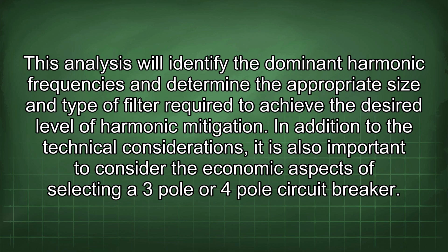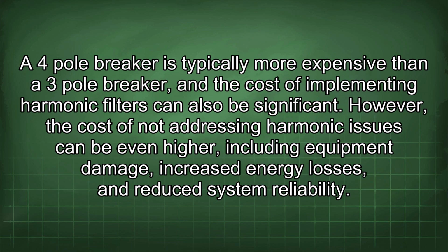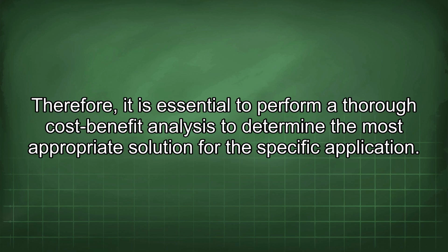In addition to the technical considerations, it is also important to consider the economic aspects of selecting a 3-pole or 4-pole circuit breaker. A 4-pole breaker is typically more expensive than a 3-pole breaker, and the cost of implementing harmonic filters can also be significant. However, the cost of not addressing harmonic issues can be even higher, including equipment damage, increased energy losses, and reduced system reliability.